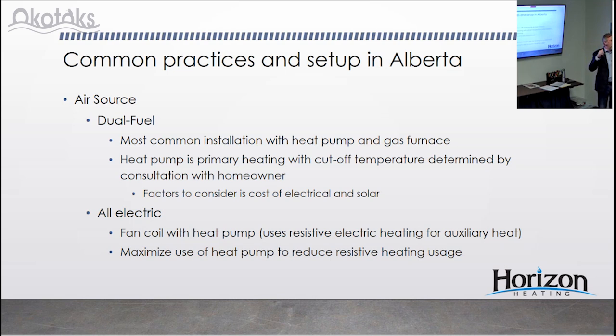So in a fan coil situation, the all electric, the coil is actually below the heating strip. So we have heat coming through the heating strip, and if the heating strip only needs to come on a little bit, it can actually stage to come on just to pick up the right amount of heat that your system needs.